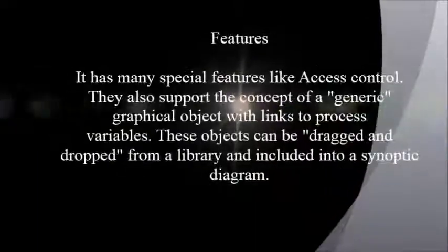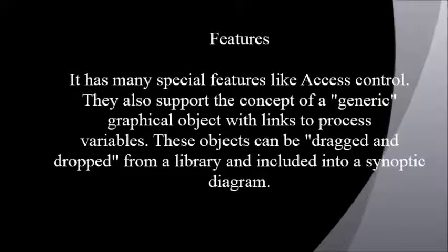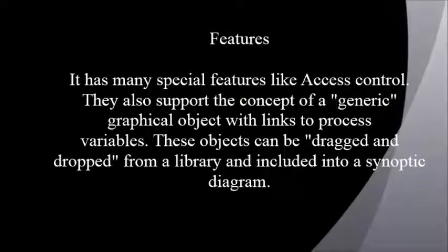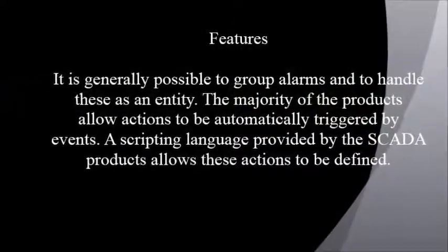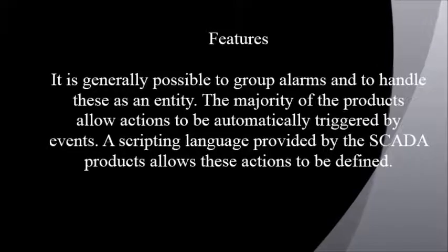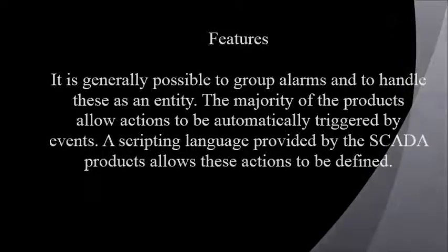Features. SCADA has many special features like access control. It also supports the concept of a generic graphical object with links to process variables. These objects can be dragged and dropped from a library and included into a synoptic diagram. It is generally possible to group alarms and handle these as an entity. The majority of products allow actions to be automatically triggered by events, and a scripting language provided by the SCADA products allows these actions to be defined.